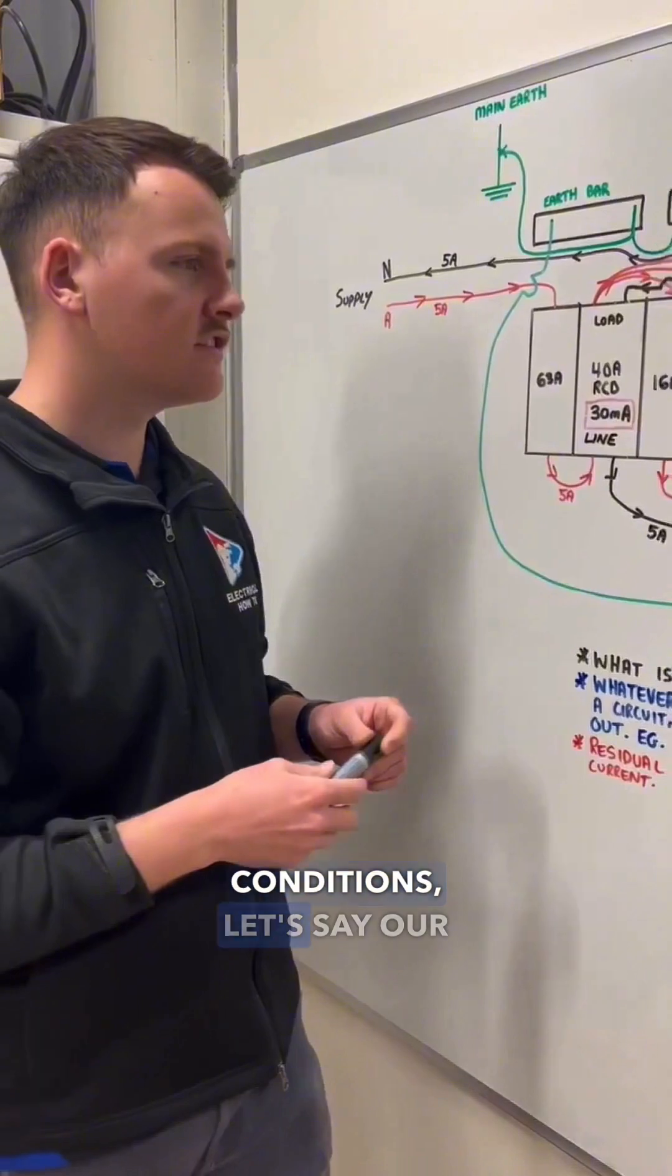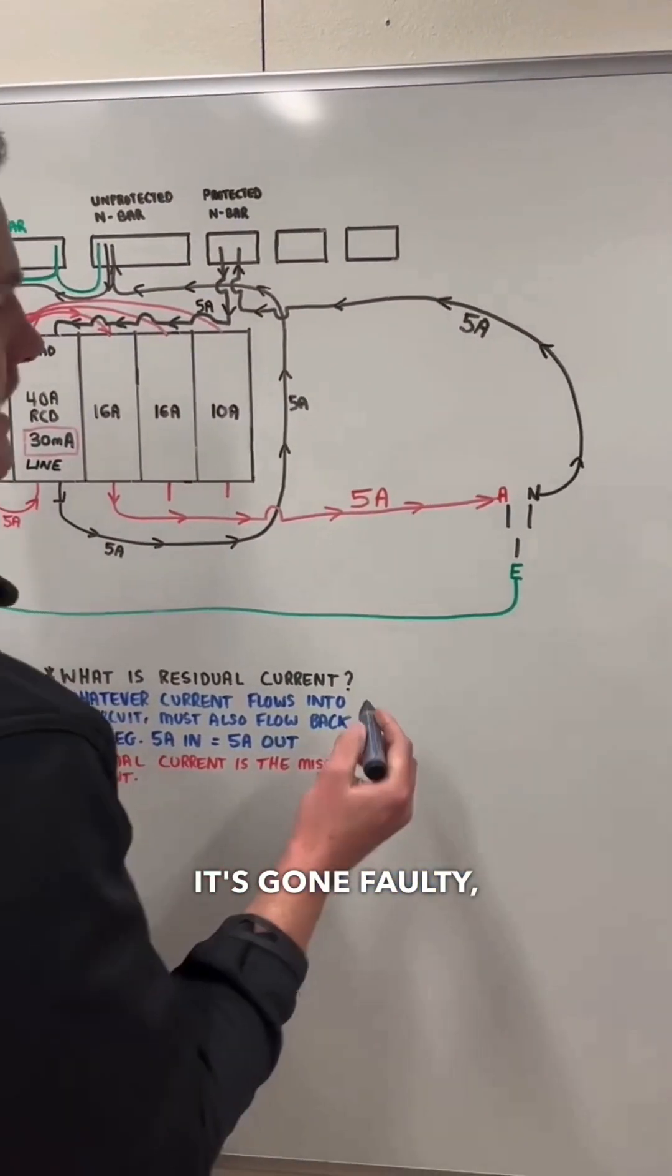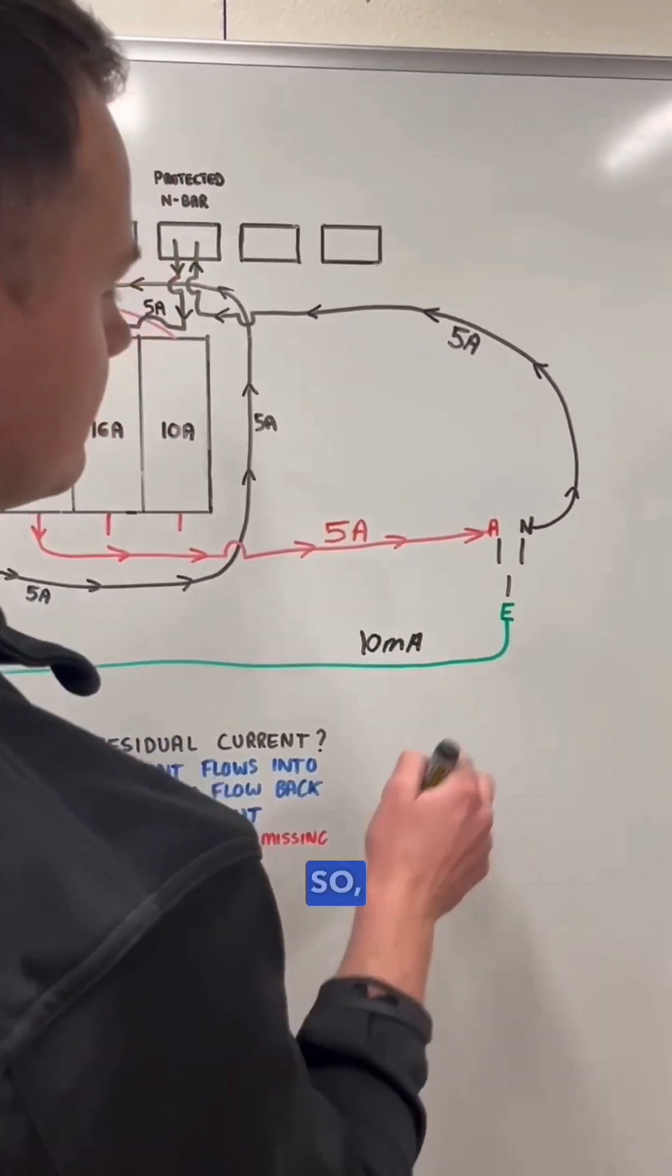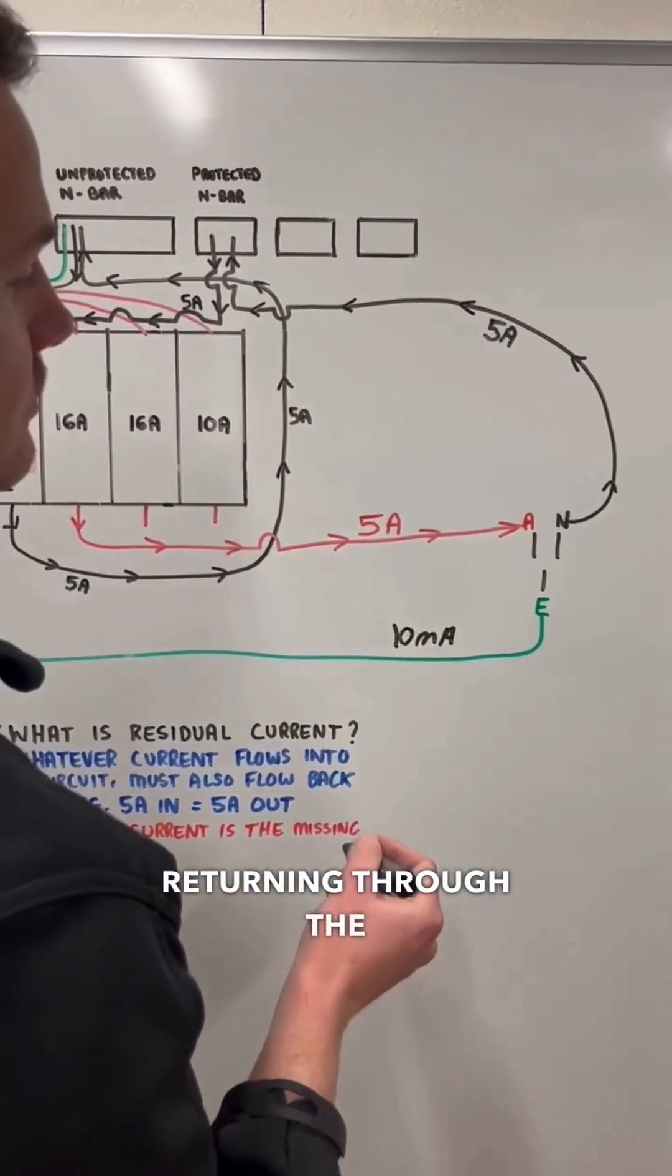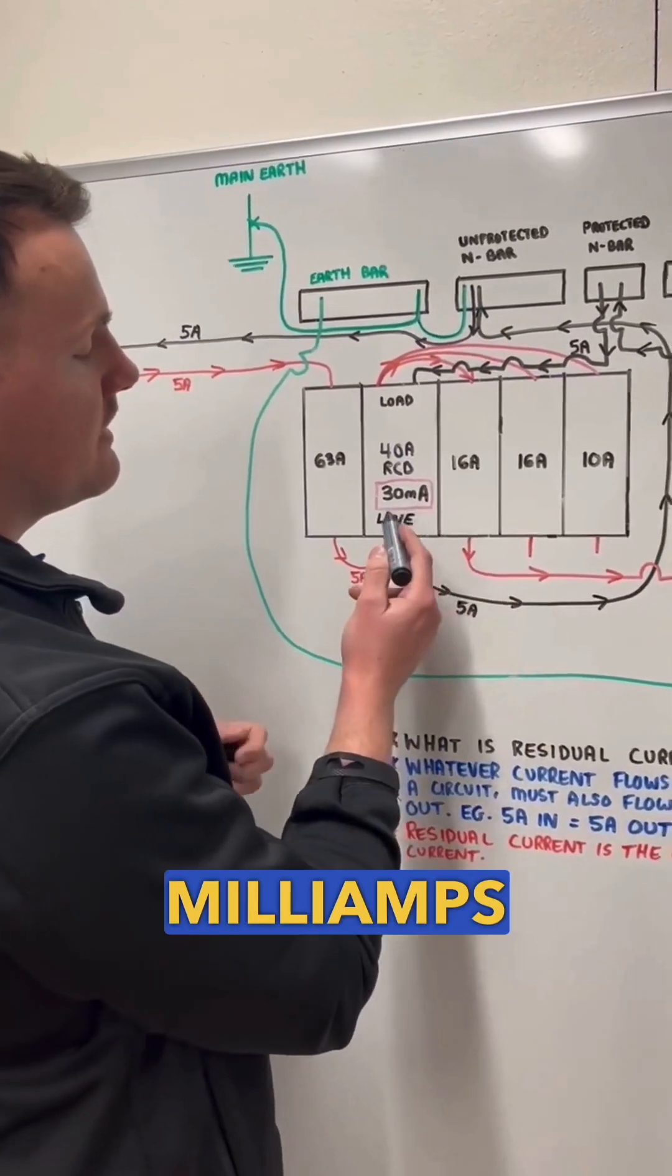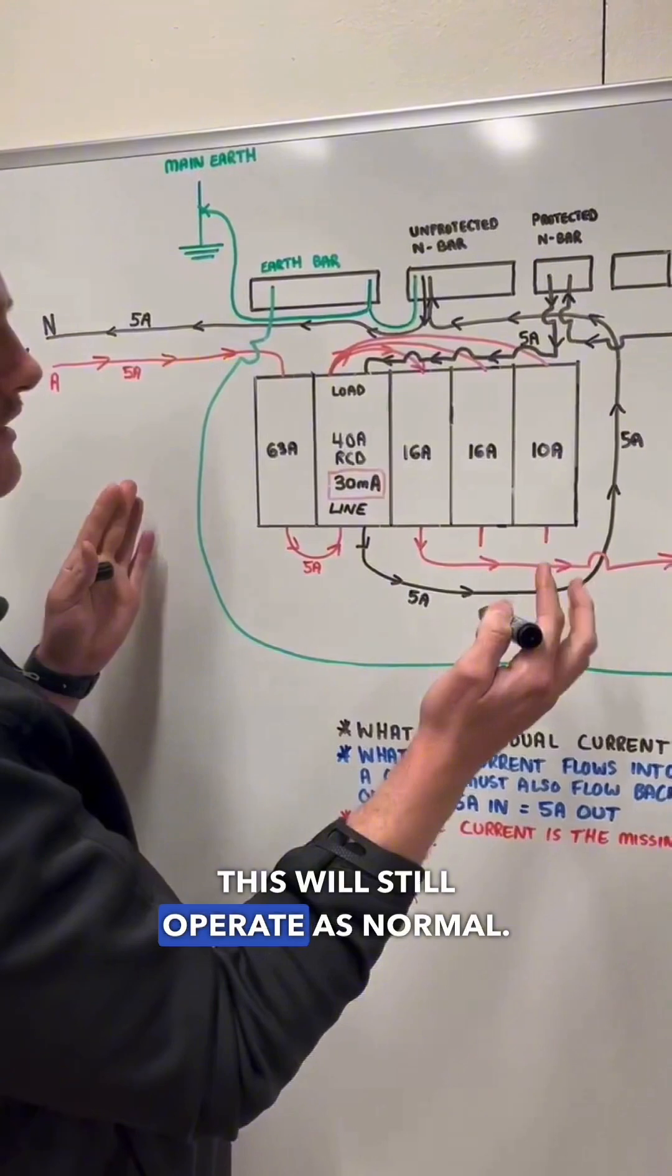Under fault conditions, let's say our hammer drill might be getting a bit old or it's gone faulty and we've got 10 milliamps travelling back through our earth. So now we're missing 10 milliamps returning through the neutral. Our RCD is still not going to trip because it's looking for an imbalance of 30 milliamps or greater. So this will still operate as normal.